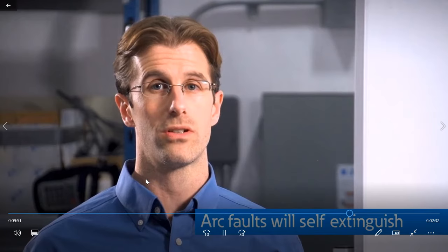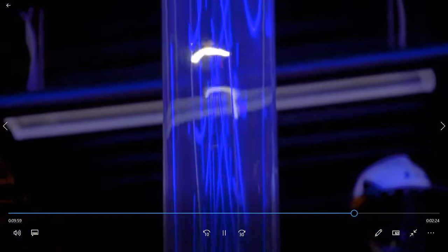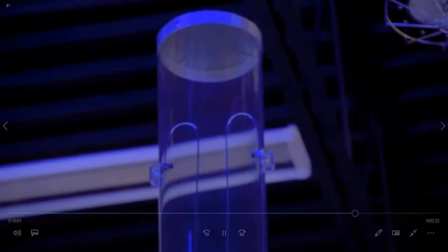Second, typical arc faults will eventually self-extinguish. That is, if you ignite an arcing fault inside any piece of equipment and supply it with current and voltage for an unlimited period of time, the arcing fault will self-extinguish.